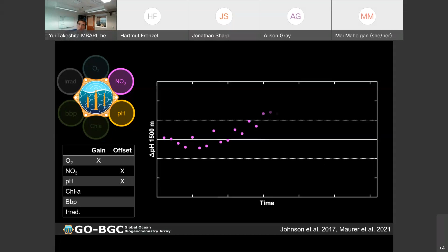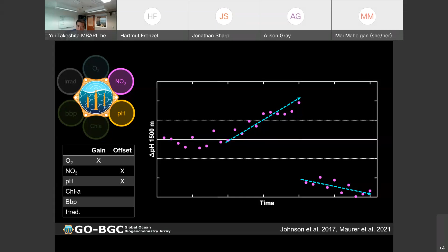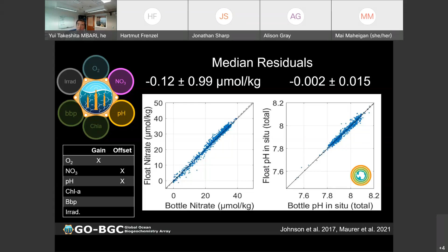It's not uncommon to see jumps in data like this, maybe due to things getting caught in the optics of the nitrate sensor. That is why we do a piecewise linear regression, so we can account for these jumps. After applying this data adjustment, this is another validation plot, nitrate on the left and pH on the right. The median residuals for nitrate are about 0 plus or minus 1 micromole per kilogram, and for pH about 0 plus minus 0.015. Using the same logic, assuming half of this variability is due to spatial and temporal variability, we think the nitrate and pH data are accurate to about 0.5 micromole per kilogram and about 0.007 for pH. I don't have the N, but these are hundreds or maybe thousands of discrete samples for each of these parameters.